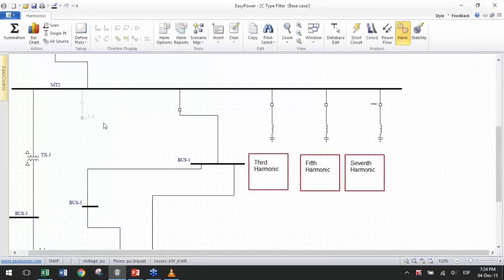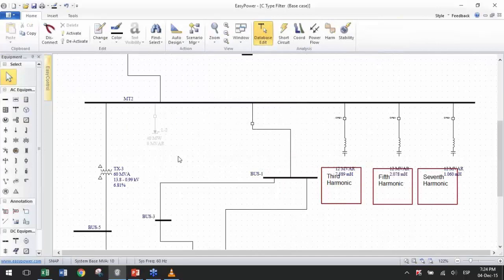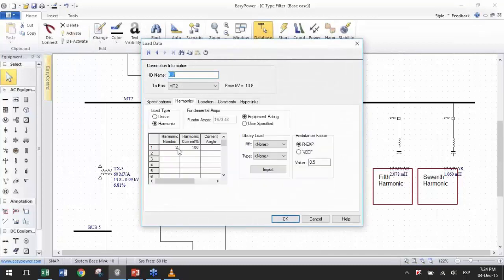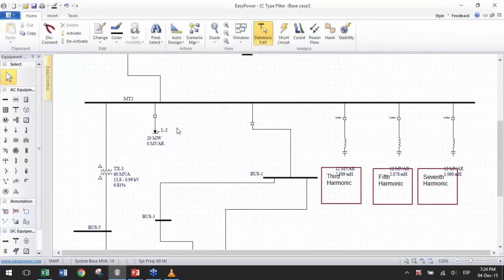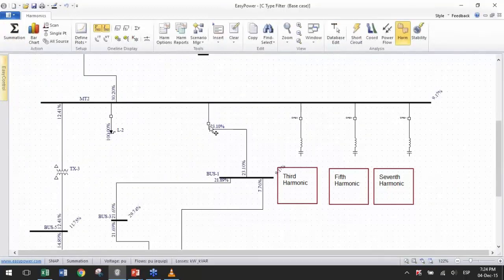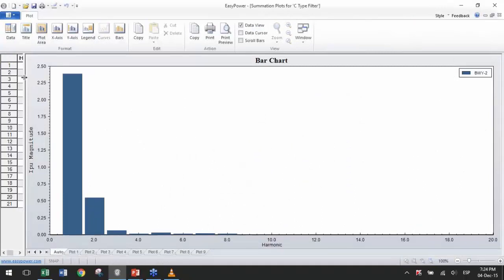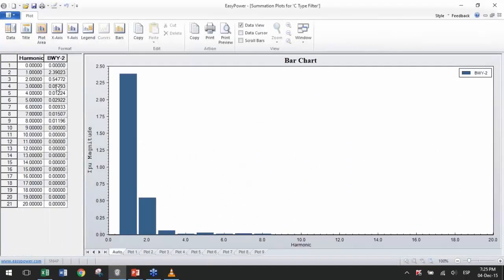And to make an example out of this, I'm going to make a truly worst case scenario where I'm going to place a lot of harmonic current just from the second harmonic, maybe a 40 megawatt system, let's say 20. So in all, it's a lot of harmonic current. So when I make the summation, I find that I have quite a lot of distortion. And another way to see if the filter is working is to check out the current that it is drawing. The second harmonic filter is mainly drawing second harmonic current.